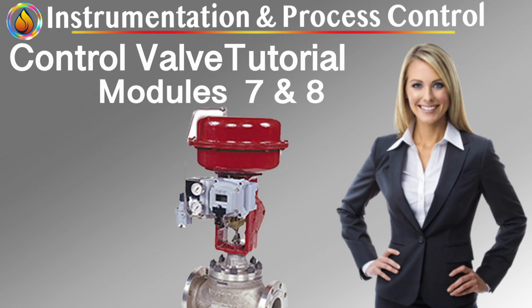Good control requires both simultaneously. Static gain versus dynamic gain. This distinction is where many engineers lose clarity. Static gain, the relationship between input signal and final valve position, governs steady-state accuracy, important for repeatability and offset reduction. Dynamic gain, how aggressively the positioner responds to change, governs overshoot, oscillation, and settling time, critical for fast loops and disturbance rejection. A positioner with excessive dynamic gain will amplify noise and induce oscillations. One with insufficient gain will make the valve sluggish and unresponsive. The correct balance is process-dependent, not universal.